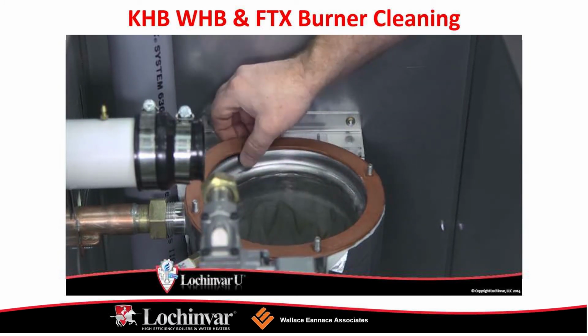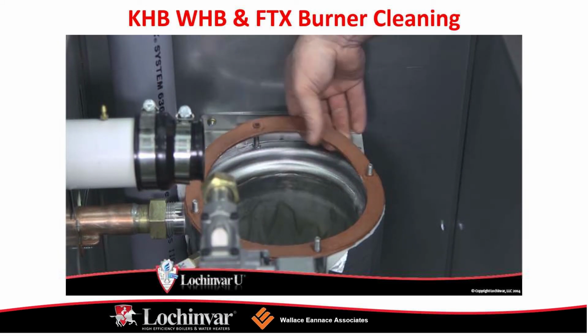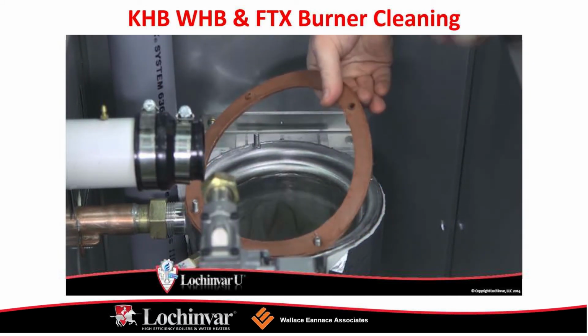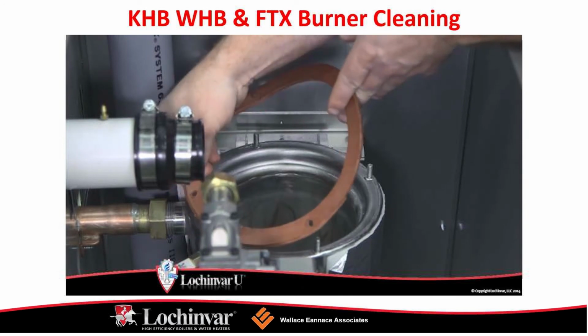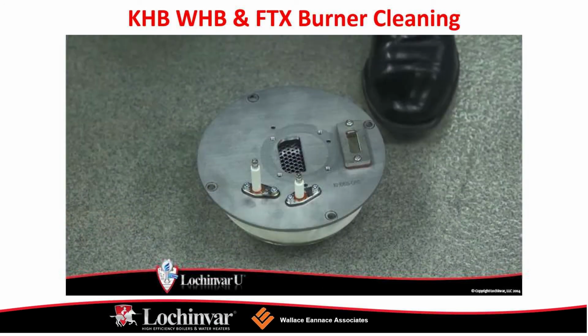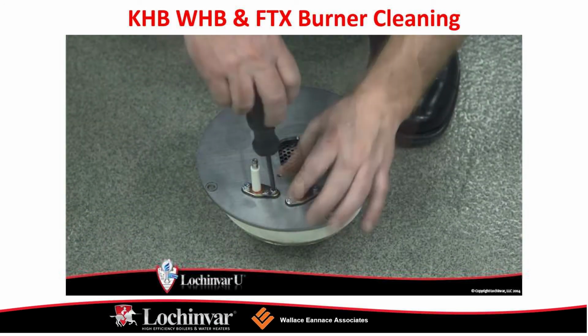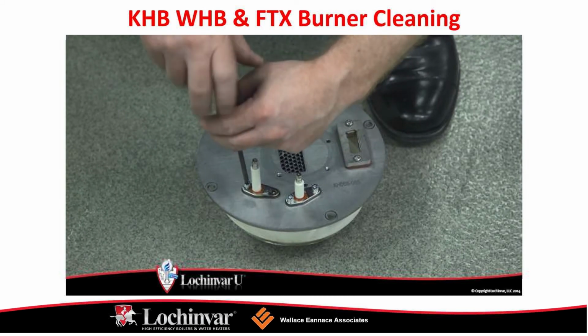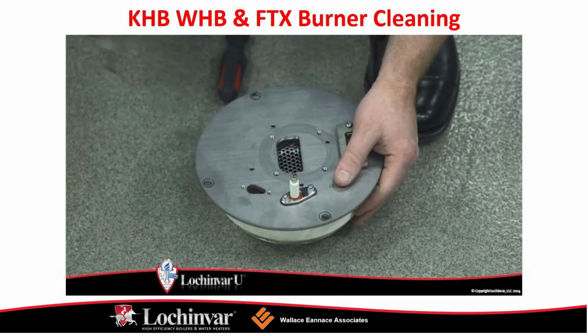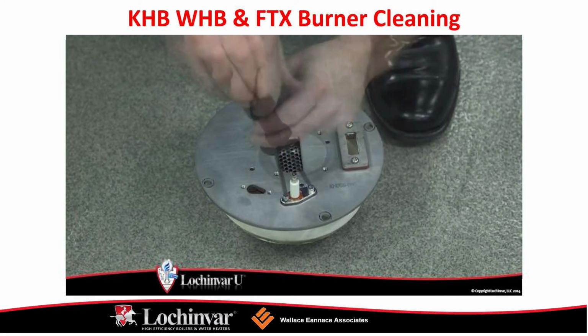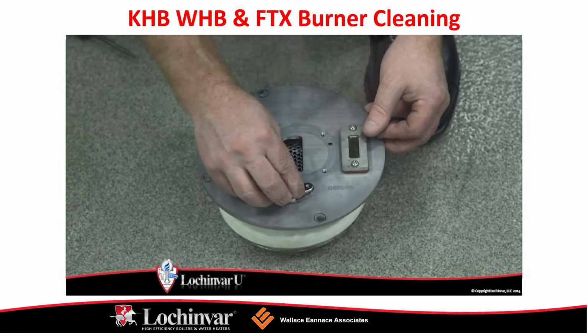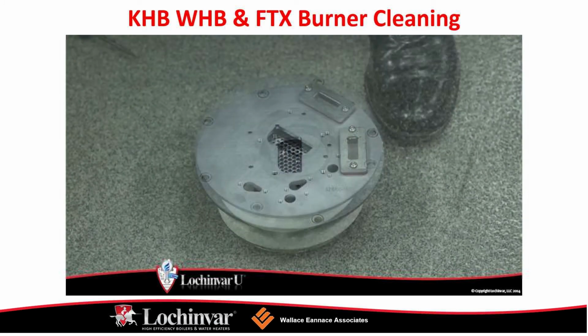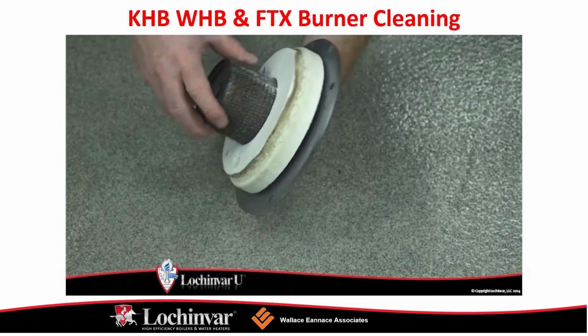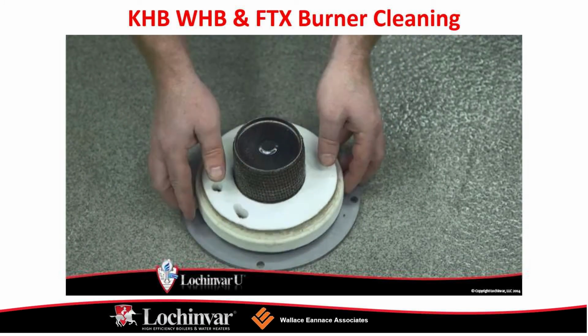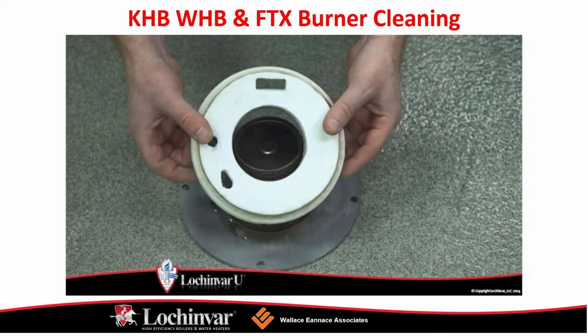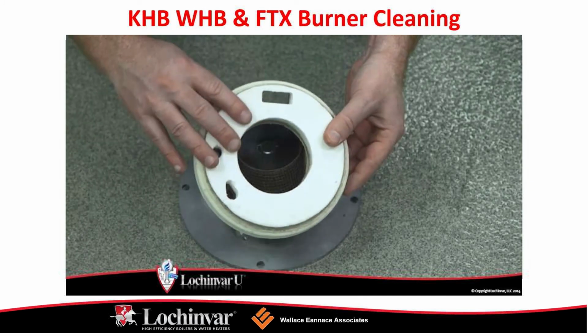Next, remove the rubber hose from the air intake pipe and loosen the band clamp securing the air inlet to the Venturi. Now, loosen the union on the Venturi. You should now remove the 4 Allen head screws securing the combustion blower to the unit. You can now slide the combustion blower and Venturi assembly to the right and remove from the unit.